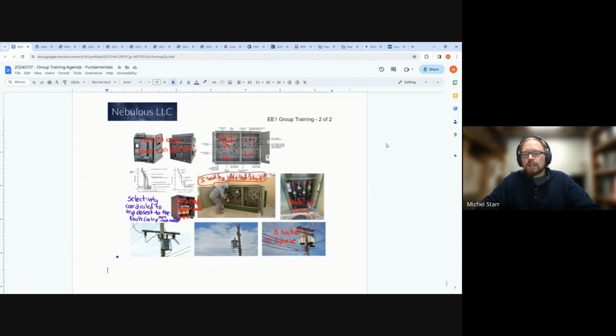It really depends on the type of equipment for the frequency, but it covers things like yearly visual inspections, maybe every two years a mechanical inspection or an equivalent thermographic inspection. If you're doing thermography, it means there's live load and heat present. Otherwise you might shut down and use a low voltage ohm meter, different from a multimeter, which can detect very small differences in resistance, showing high resistance or a need to tighten something that isn't torqued correctly.